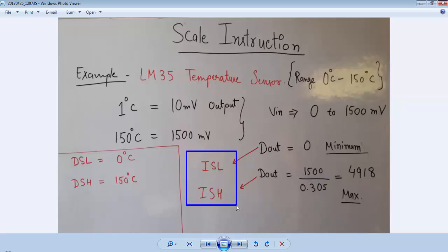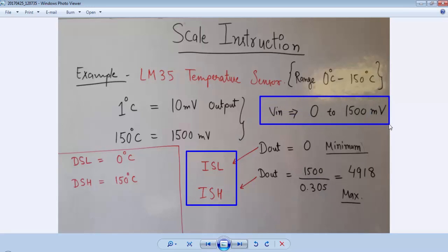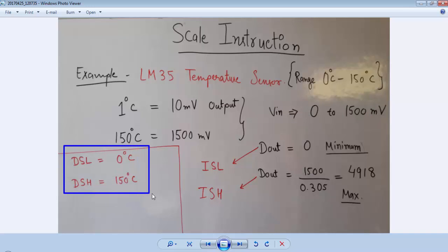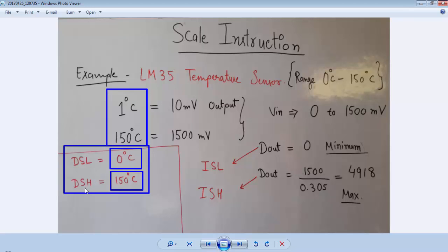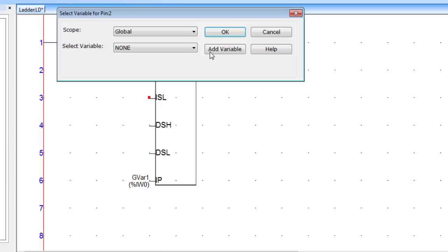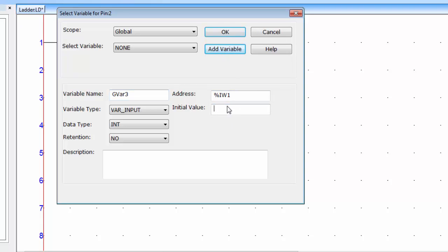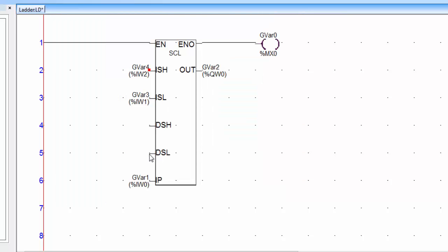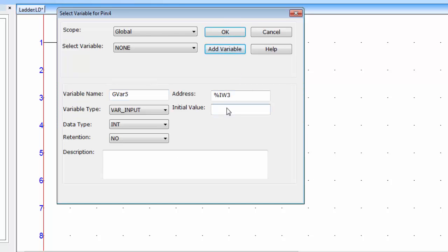The ISL and ISH values of the scale instruction depend upon the V_in minimum to V_in maximum values. DSL and DSH — display scale low and display scale high — depend upon the required display parameter. Since we want to display temperature from 0°C to 150°C, DSL is 0 and DSH is 150. Double click ISL, add variable, initial value 0. Double click ISH, add variable, value is 4918. Double click DSL, add variable, initial value 0. DSH is 150 — click OK.